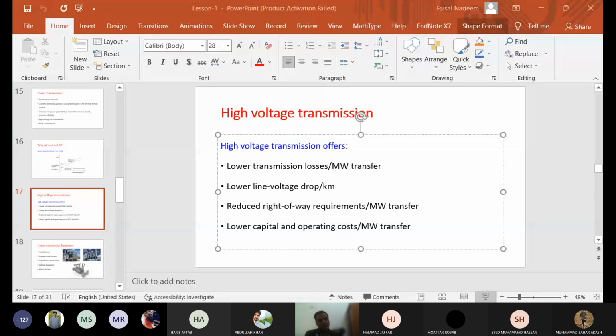Transmission voltages are around 220 kilovolts and 500 kilovolts. So at the generating station we need a step-up transformer to step up the voltage from 9.3, 11, 18, or 22 kilovolts to 220 or 500 kilovolts. There, power transformers are used to step up the voltages, and at grid stations they are used for stepping down the voltages, from 500 to 220, 220 to 132, 132 to 11, and so on. This is the distribution transformer.